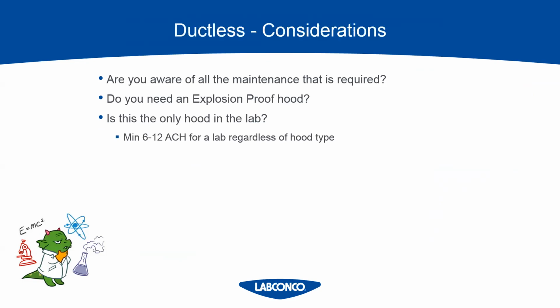Is this your only hood in the lab? If so, I strongly suggest going ducted. The reason why is that it's going to contribute to your air exchange rate, which is about 6 to 12 air changes per hour, called out by ASHRAE for a lab. And you don't have to worry about being so super careful with what you put in the hood. There are a lot of reasons why, if it's the only hood in the lab, it would be beneficial to go ducted, because what happens if a year later your application changes and guess what? It's not compatible with a ductless hood. Then you're left where you started.